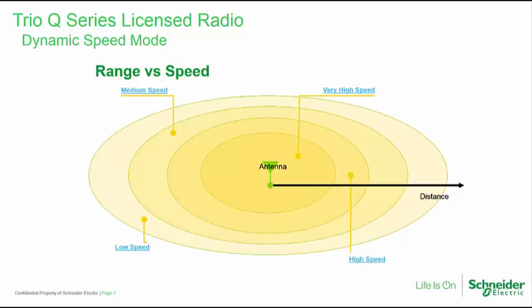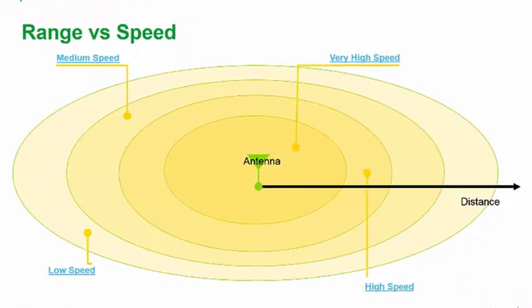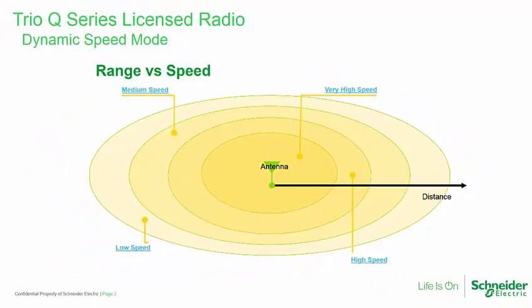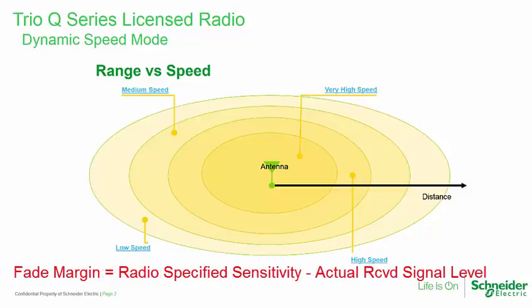Consider the example in this diagram. When communicating, radio signals from the access point radio diminish in strength as the signal propagates over distance. In a system without dynamic radio data rate selection, the user would need to configure all radios in the system for a data rate which would provide reliable communication to the most distant site. In such systems, a minimum of 20 decibels fade margin is typically designed into the system. Fade margin is the difference between the radio's specified sensitivity — its minimum ability to hear — and the actual received signal level.